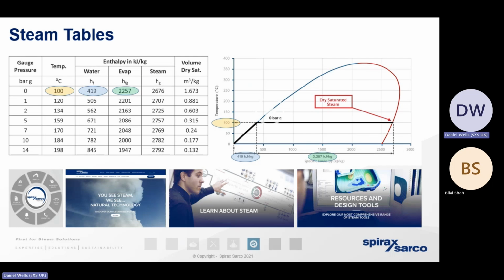So aside from the mechanical issues, the erosion, the corrosion, the water hammer, it's also likely that we're going to experience inefficiencies. So remember, we've got steam at 10 bar gauge, 184 degrees, leaving the boiler, coming into the pipework, traveling 5,000 meters around our client's site. It's a carbon steel infrastructure. We're going to have missing, damaged, substandard insulation. That pipework's one big radiator. We're going to get a lot of heat loss.